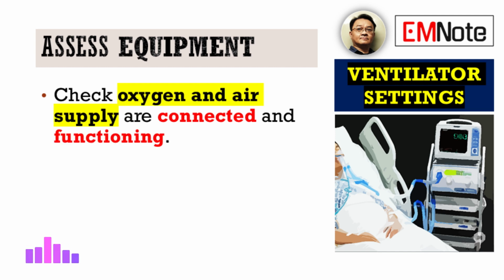Next up, the gas supplies. These are quite literally the essential elements, the lifeblood of the system. How do we check those? Right. You absolutely must check that the oxygen and the medical air supplies are securely connected to the ventilator. These are usually high-pressure hoses, right? They attach to specific ports, typically on the back of the machine. Loose connections can lead to insufficient gas delivery or even a complete loss of gas flow. That would basically render the ventilator useless.